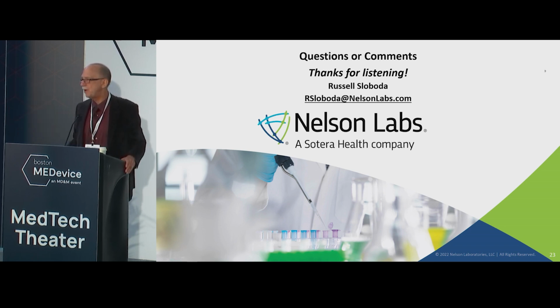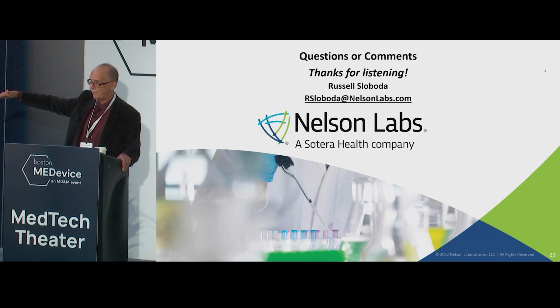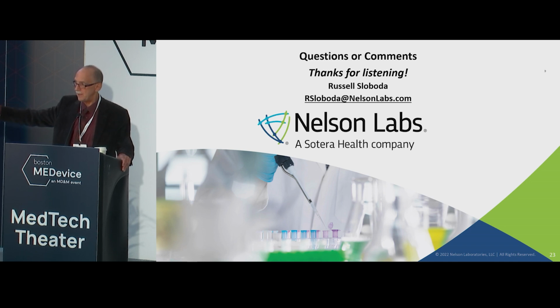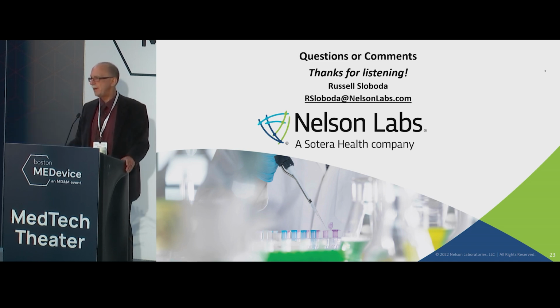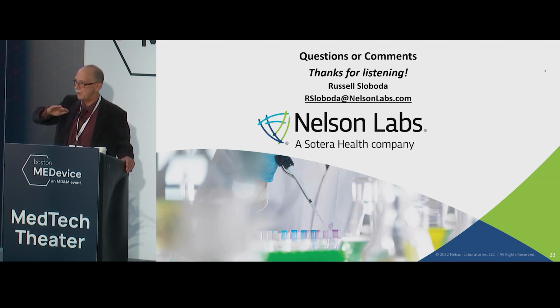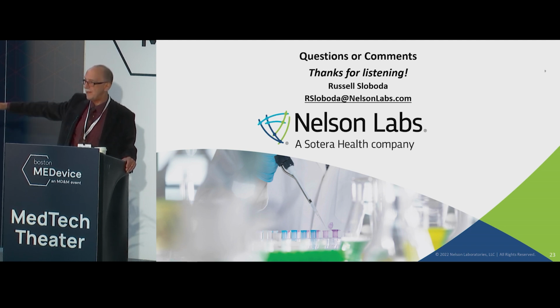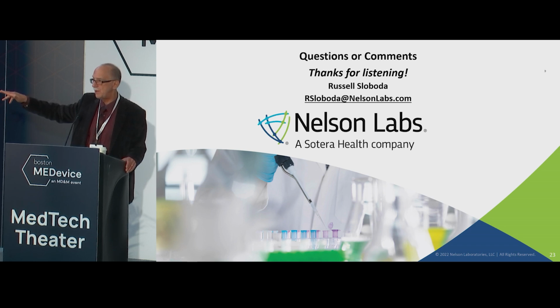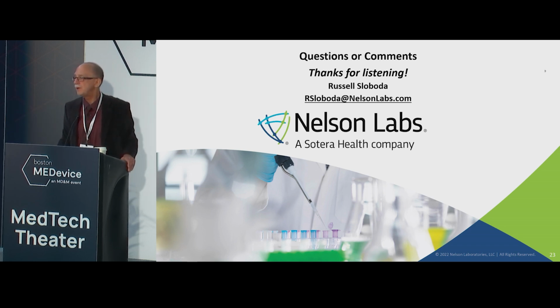That approach has probably zero chance of being rejected because that's real clear. The concept of unknowns is another story. What I have found in practice is that if you can show the unknown is tapering off on release kinetics and it drops below whatever the longest term is that's applicable to the unknown. So for a permanent implant, it has to get below 1.5 so that you can prove that the average over the entire lifetime cannot be over 1.5 microgram per day exposure. So if the last time point falls below 1.5, the first few you're going to be able to justify.